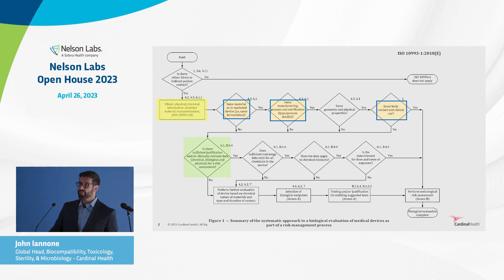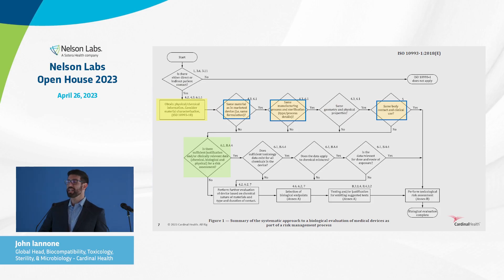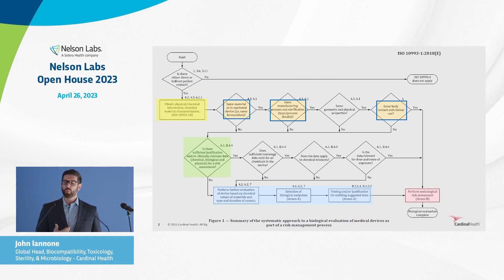In that information gathering phase, do I have enough information? Do I have enough to justify the use of that device? Do I have enough information about the chemical constituents that would be imparted — leaching onto that device? Do I have enough information from material suppliers? Do I know enough about the formulation of that device, the way it's manufactured, extruded, and so on? Once we do that evaluation, that's when we start supplementing the gaps — not just diving straight into a study, but understanding what we had, what we need, and where are those gaps. What testing then needs to be done?